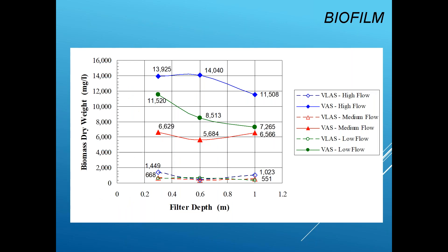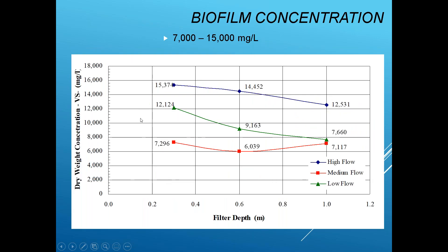Biomass density measurements show that different flows through the system generate different levels of biofilm. Even at low flows, biofilm is still present — just less dense. Concentrations of biofilm solids range from 7,000 to 15,000 milligrams per liter, providing an excellent means of treating wastewater.